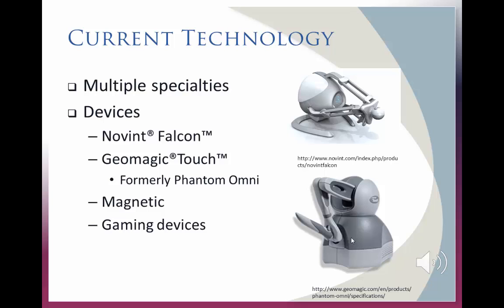Magnetic levitation haptic devices are a relatively new technology involving the use of strong magnetic fields and a movable floater that floats between the magnets and is optically tracked. This may increase the ease of motion as the device is not rigidly tethered to a base as are the conventional haptic devices, while still being able to provide force feedback.